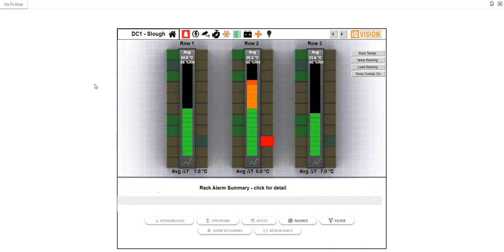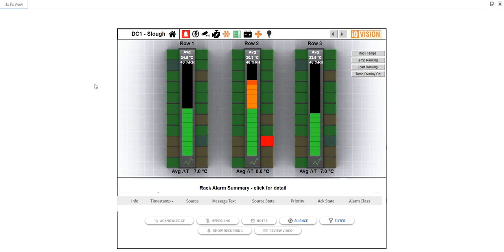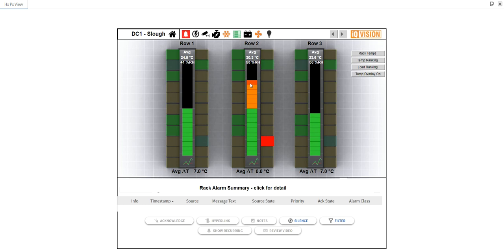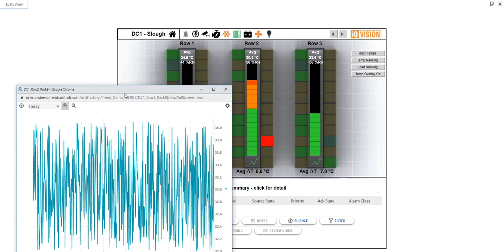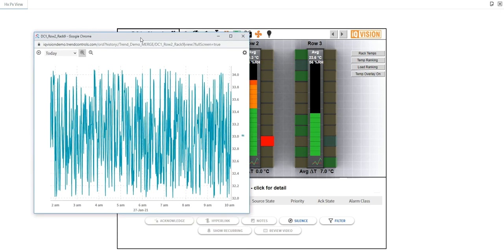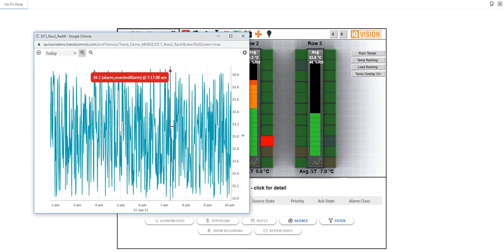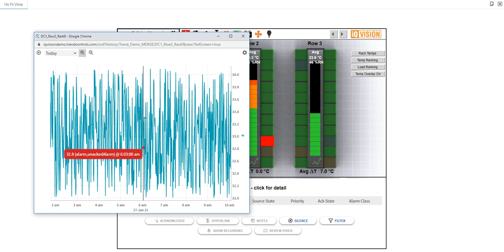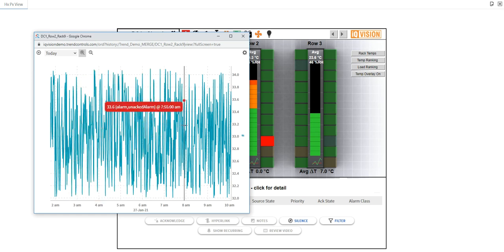If I move on again, we have an overview of the racks themselves. Again, a very stylized and simplified view. Nothing photorealistic, nothing fluorescent or flashy. Just all the data someone might need to know. No photographs and that sort of thing, it just confuses the issue. We've got some averaged out temperatures and humidities here. You can see one of them is quite high. This sliding graph up the middle here is in the red. So we have got a problem somewhere in that rack. It's quite obvious it's somewhere in that row, and it's quite obvious it's this rack here. If I actually click on it, we can see a graph of the temperatures in that rack. You can see because of the red flag here, everything is in alarm. So the rack is quite warm.